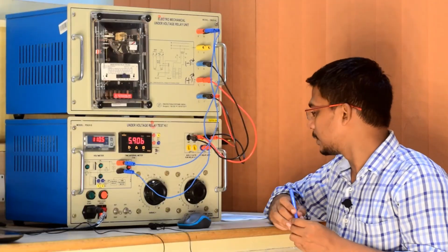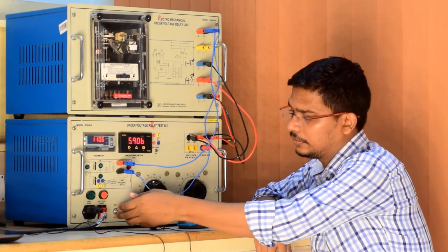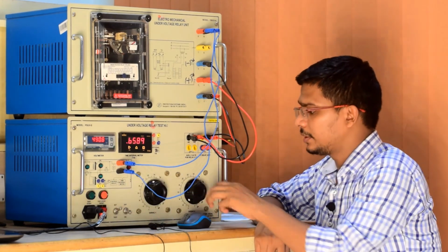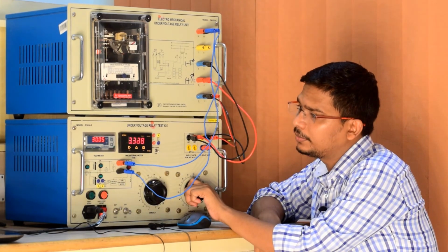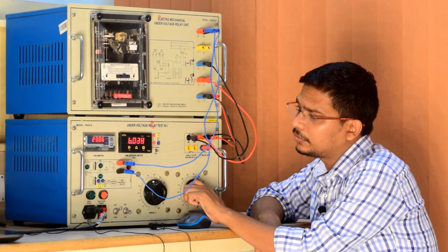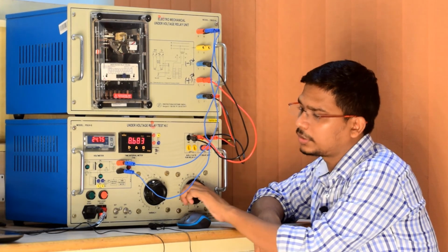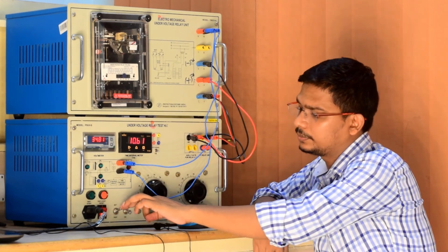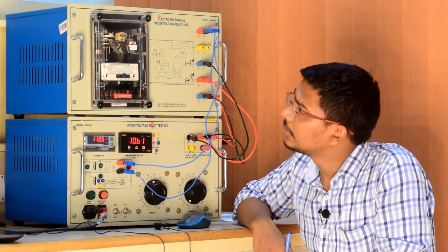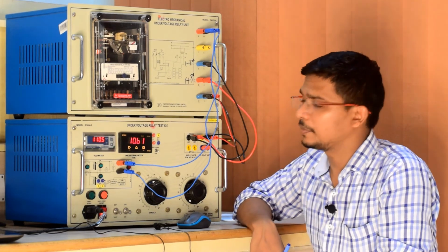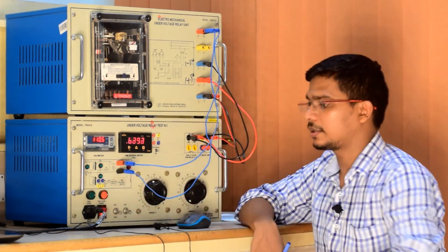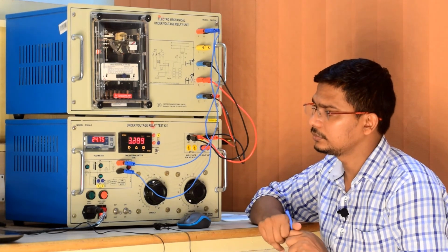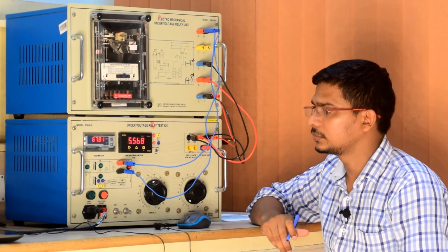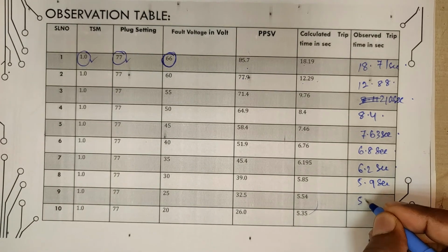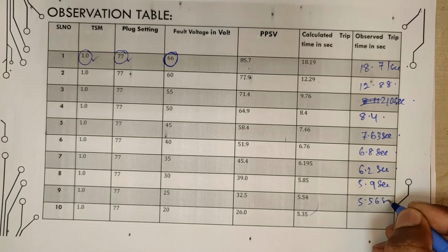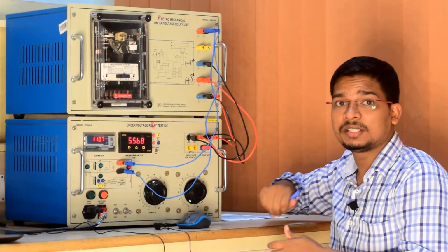So the next observation is 25. Turn off, put to test, then start. We have to apply 25 volt. Turn off, put to test and wait. Yes, the disk is moving. Okay, it came to standstill position. Then test, start. We got 5.5 seconds. Our expectation is 5.54 seconds. So 5.6 seconds, exactly as expected.